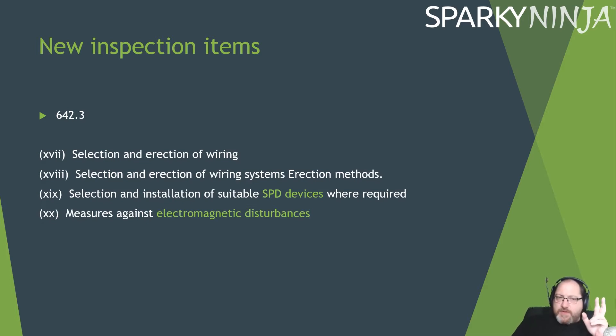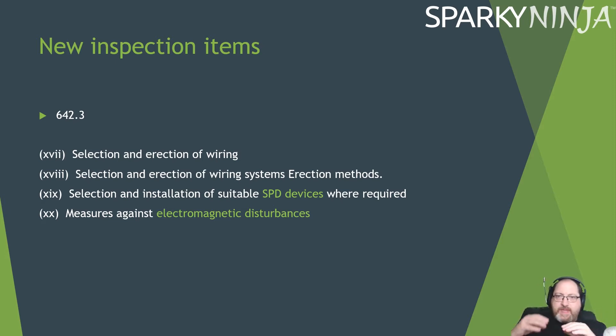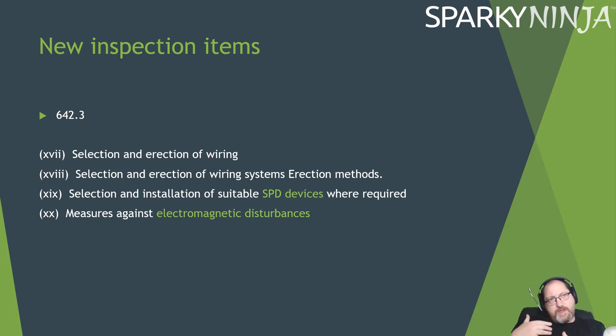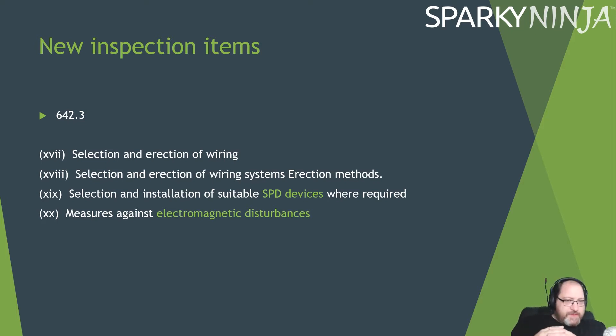We have a couple of new inspection items at 642.3. The old list is there, but they've added at the end: the erection method has been changed to selection and erection of a wiring system's erection method. We've also got — because they were introduced in Amendment 3 — selection and installation of suitable SPD devices where required, and measures against electromagnetic disturbances. So those have been added to the inspection items.